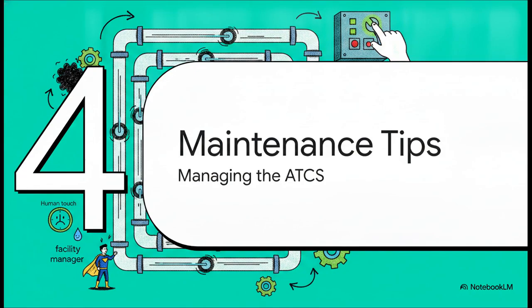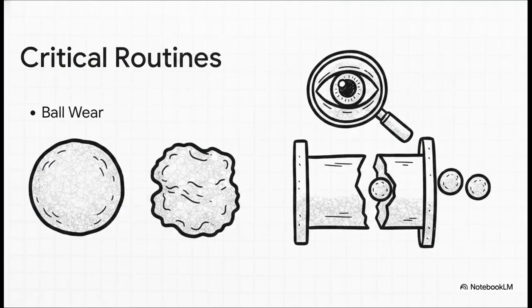Maintenance and management tips. Because as great as this is, the system isn't just pure magic. Facility managers really have to act as the sidekick here, and there are two critical management routines they must follow. Number one, monitor ball wear. These sponge balls are constantly squeezing through tight metal tubes, so naturally, they wear down, tear, or shrink over time. If a ball shrinks too much, it just floats lazily through the pipe without actually scrubbing anything, so operators have to regularly check their size and swap in fresh ones.